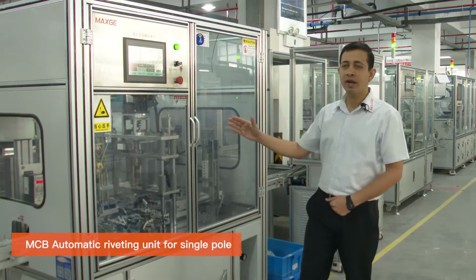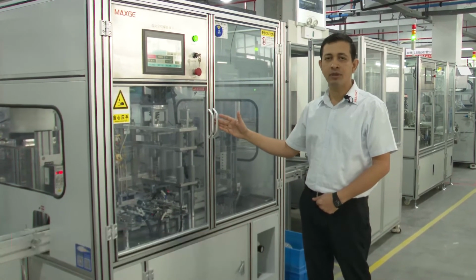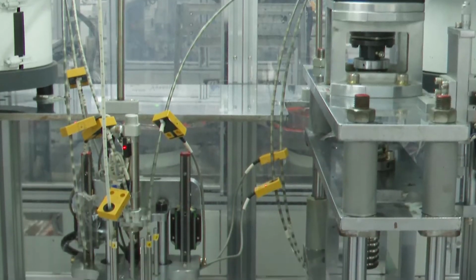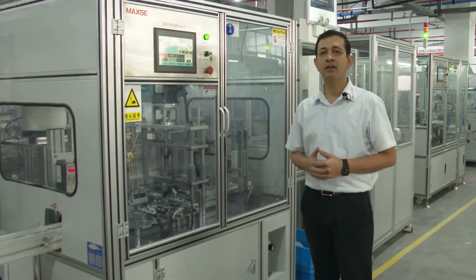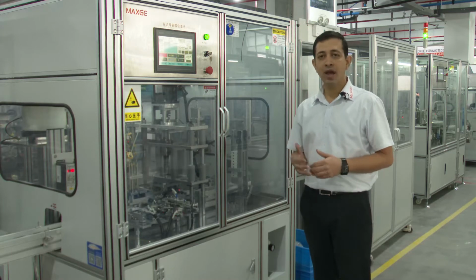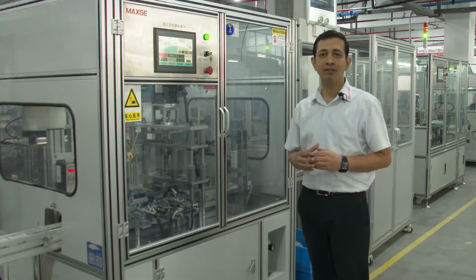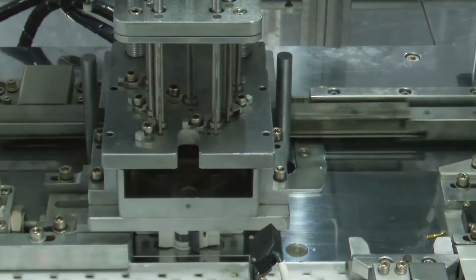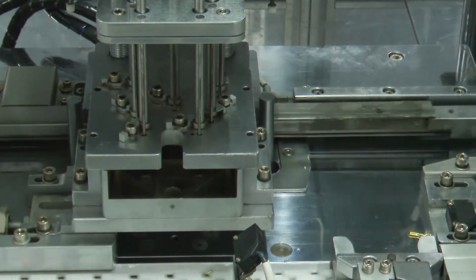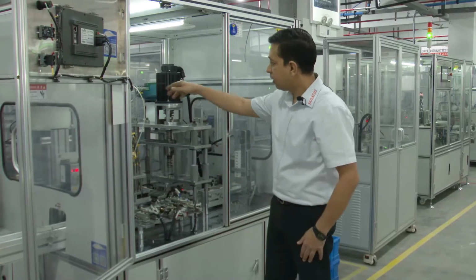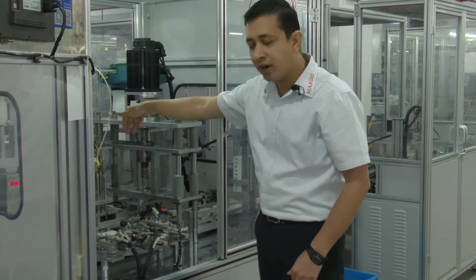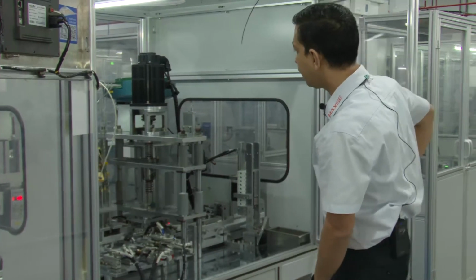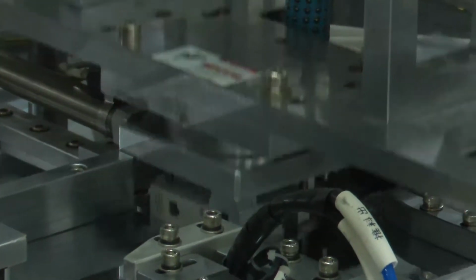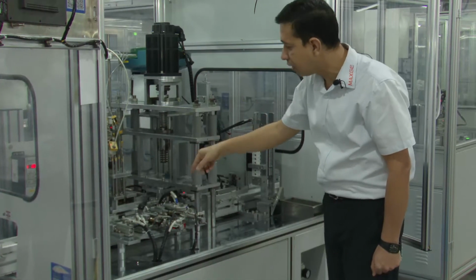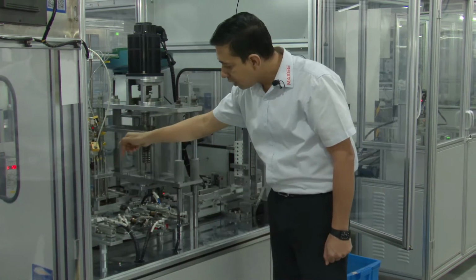Now this machine is an automatic rivet insertion machine for the MCB. In our MCB, the plus point is we have 7 rivets. As far as the competitors are concerned, they have only 4 to 5 rivets. By having more rivets, we can ensure the breaking capacity, so that during a short circuit the MCB will not explode. And this machine being automatic, this is the bowl feeder, wherein the first 4 rivets are inserted, and this is the second riveting station where the remaining 3 rivets are inserted. You can see the riveting is happening here.